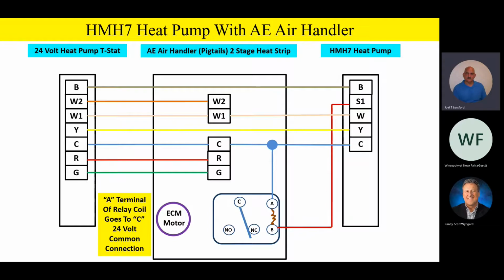And as you notice outside, there's only 5 wires outside. You have a B, an S1, a W, a Y, and a C. And by the way, that's all you need outside, 5 wires, to have full function with this unit. And we'll talk about that relay a little bit more in a little bit, but let's take a look at the common terminal on the switching contacts. That's going to tie into the yellow wire going outside for our compressor operation. So basically, anytime the compressor is running, we're going to have 24 volts on the common terminal for the switching contacts.